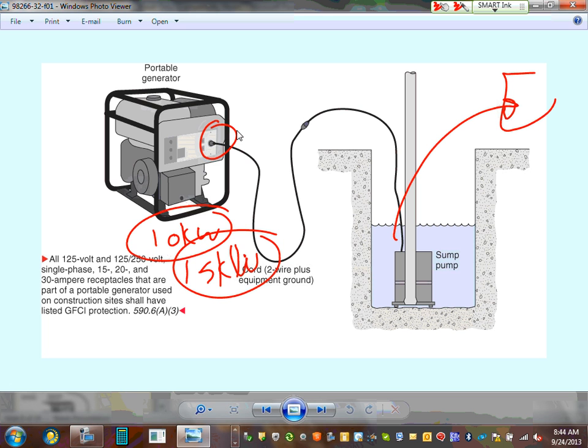The NEC code book requires the 120, 240 volt, 15, 20, and 30 amp receptacles on the generator to be GFCI, in-use cover, tamper resistant. That requirement came in 2008. So when you buy a generator, the manufacturer now has to have an in-use cover on them, GFCI, and weather resistant. Okay, so that's the cheapest that you can get.